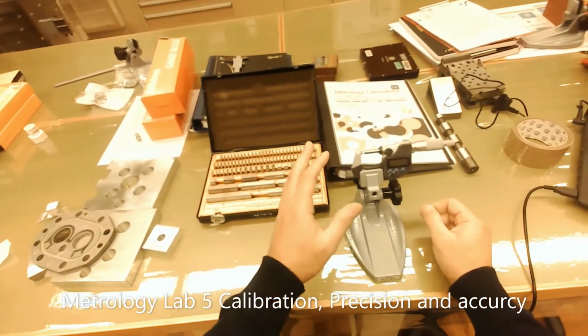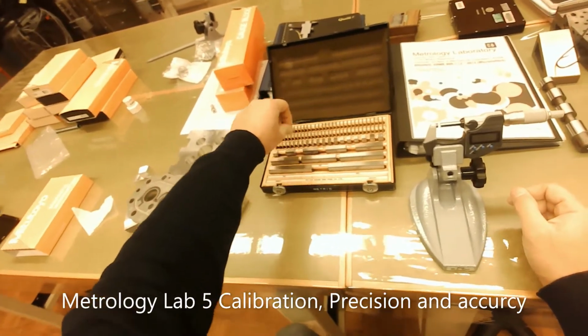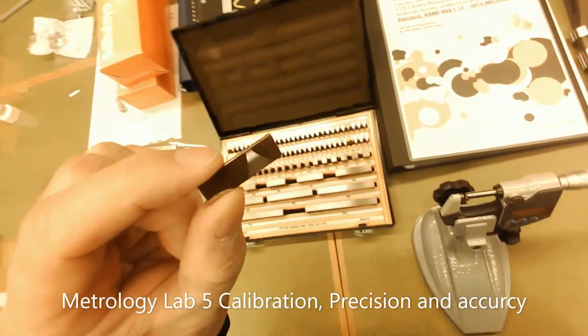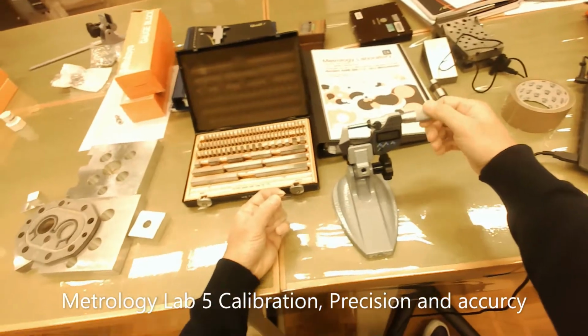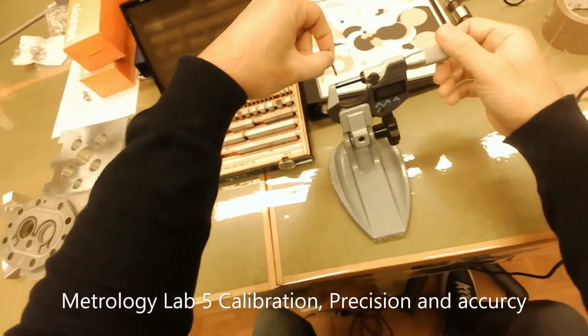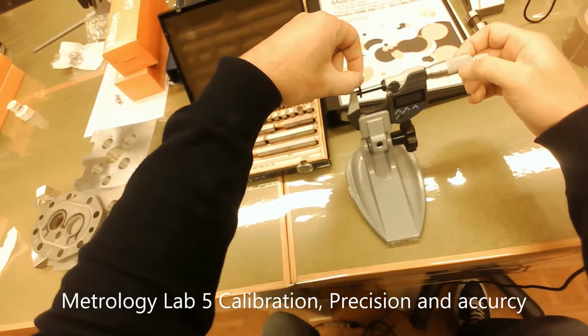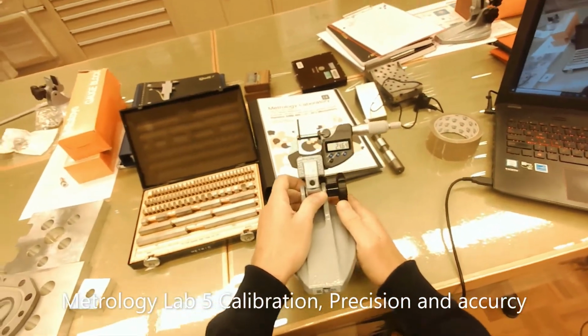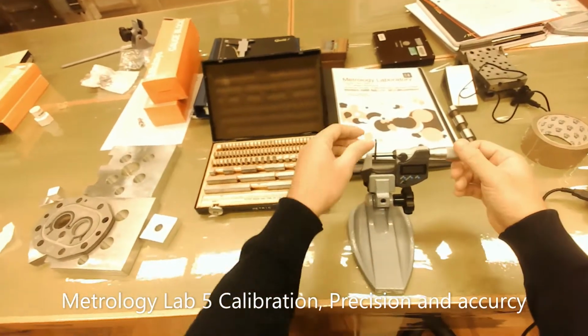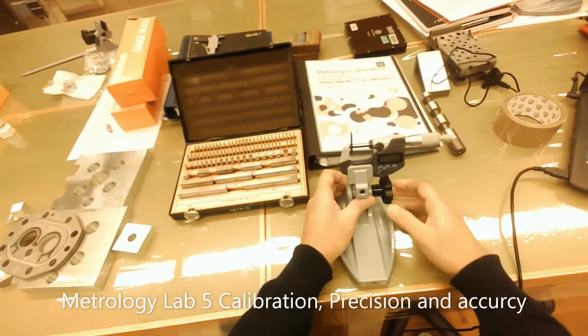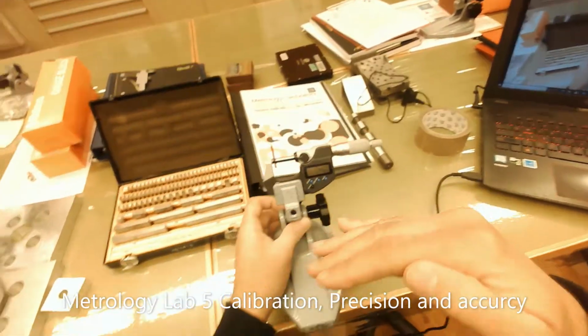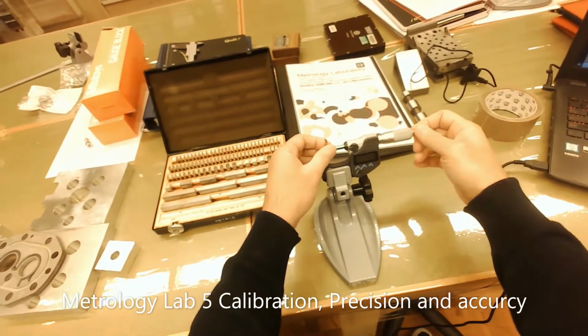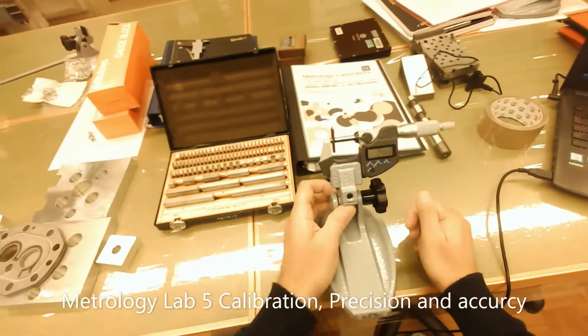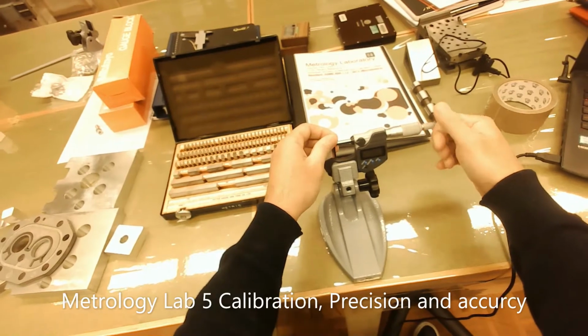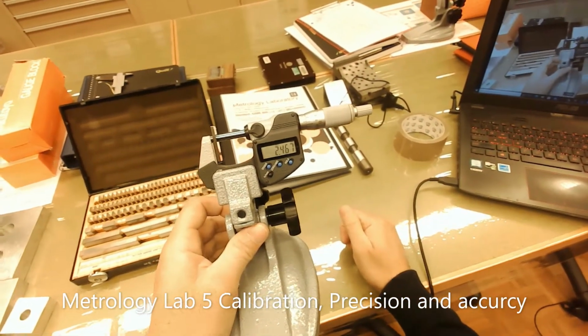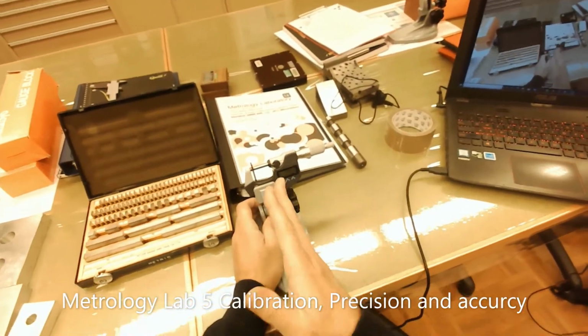Now we're talking about precision. I measure the same part multiple times. I pick one of the parts randomly, which is 2.46, and I set the value to 0. Okay, now it's 0. And I check the thickness of my part. Now the reading is 2.464. I move the part a little bit and do the reading again, and I got 2.466. Now you can see that the values are getting higher. If I put the part in this location again and take another reading, I got 2.466. Okay, I got 2.467. So the readings are changing for what's supposed to be the same thickness.